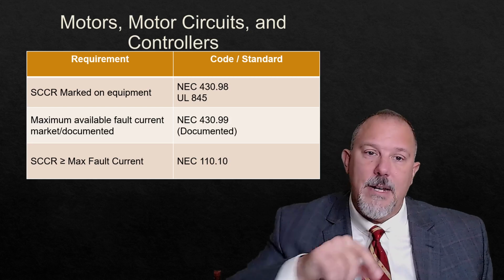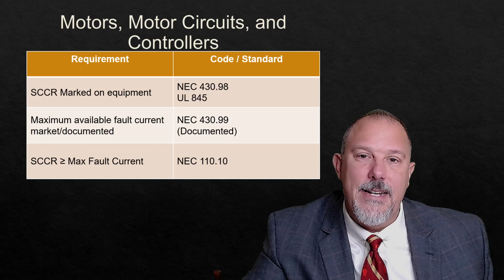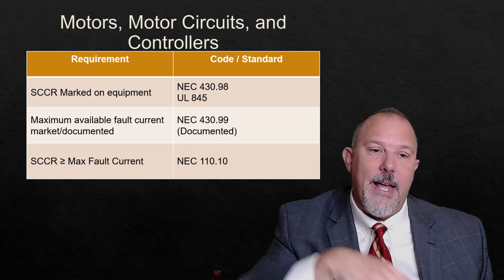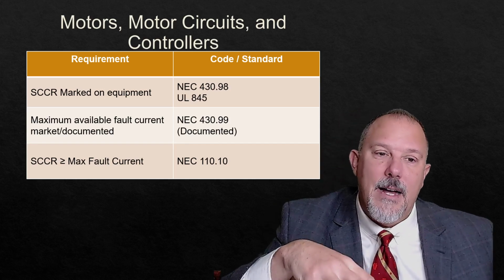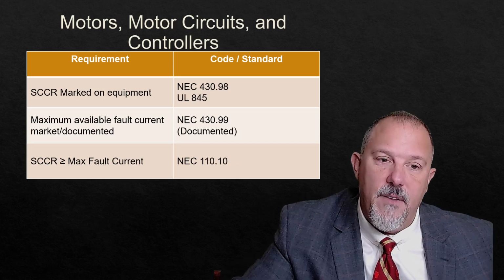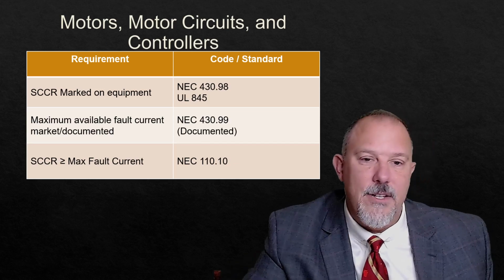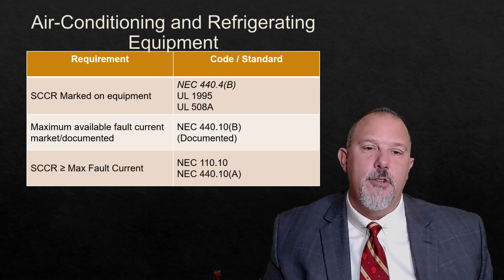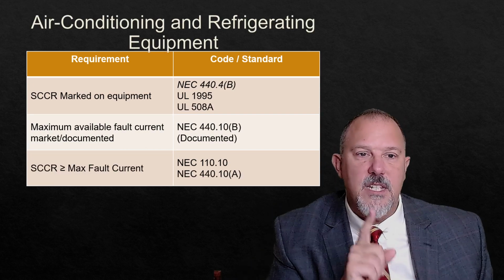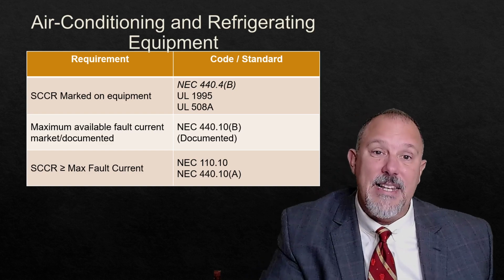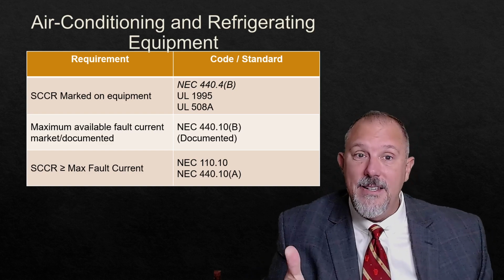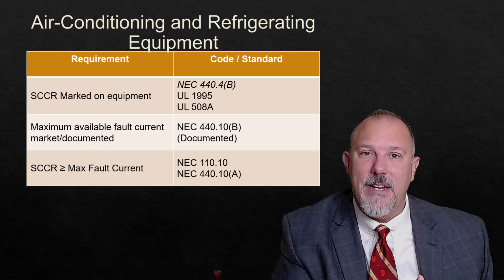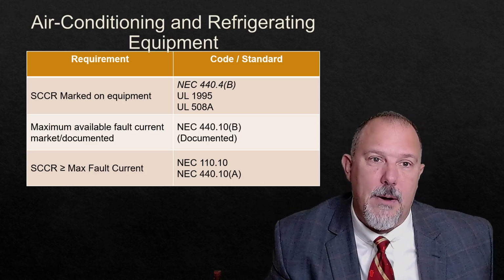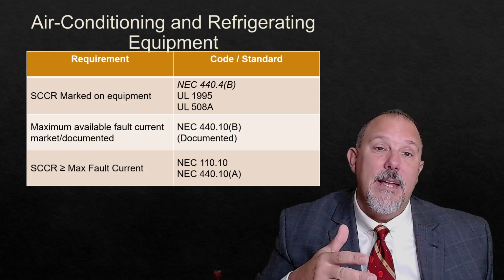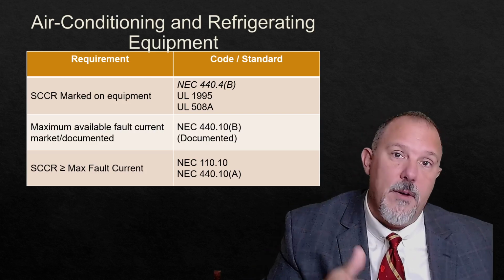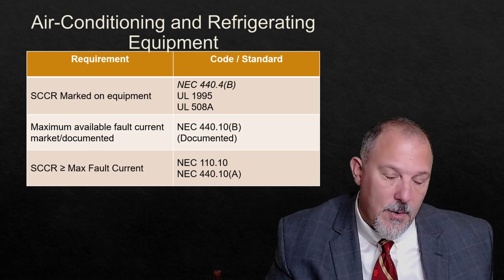The maximum available fault current has to be documented based on 430.99, and the SCCR needs to be greater than or equal to the maximum available fault current, and that's based on 110.10. Air conditioning and refrigeration equipment. The SCCR has to be marked on the equipment based on NEC 440.4B, but if you buy a listed UL 1995 product or a UL 508A product, the SCCR is required to be on the label because it's required by the listing.